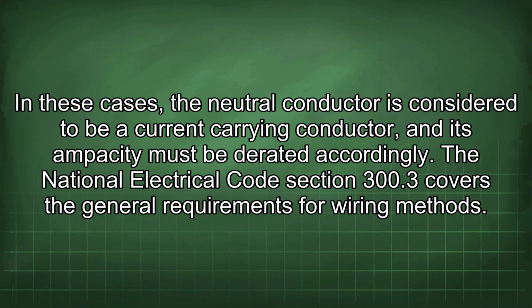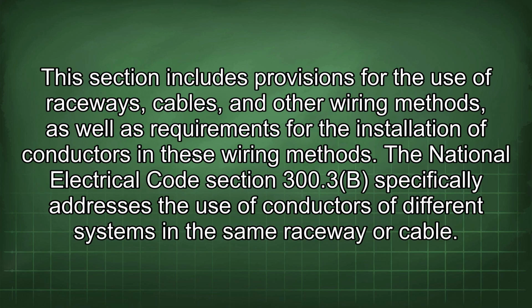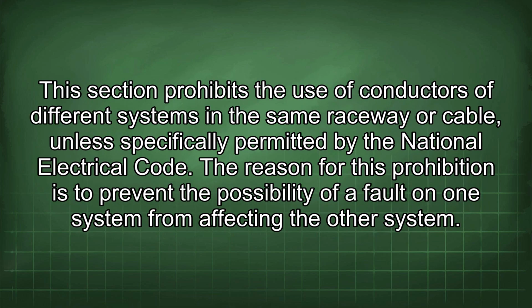National Electrical Code Section 300.3 covers the general requirements for wiring methods. This section includes provisions for the use of raceways, cables, and other wiring methods, as well as requirements for the installation of conductors in these wiring methods. Section 300.3(B) specifically addresses the use of conductors of different systems in the same raceway or cable. This section prohibits the use of conductors of different systems in the same raceway or cable, unless specifically permitted by the National Electrical Code.